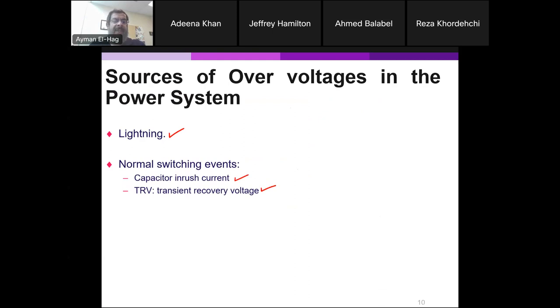And then we'll talk about the TRV, or the transient recovery voltage. TRV is a well-known term used in the literature. When there is a fault in the system and my breaker tries to interrupt this current, a very high voltage with a high frequency appears at the terminal of the breaker before it clears the fault. And we'll see what the impact is if it doesn't clear the fault. So all these things we'll talk about. This is what we'll be covering today.